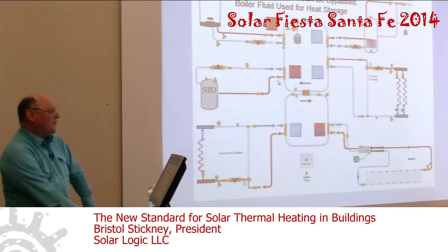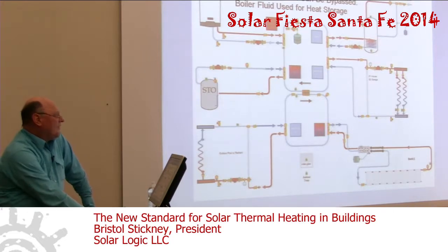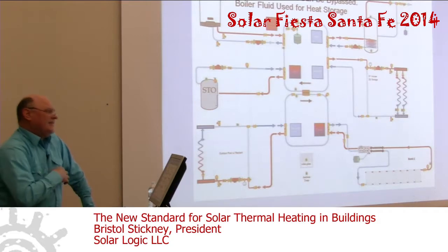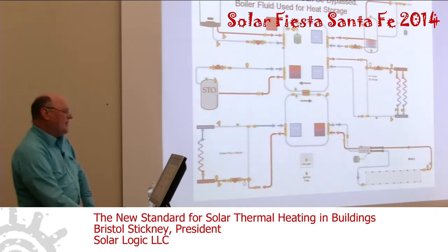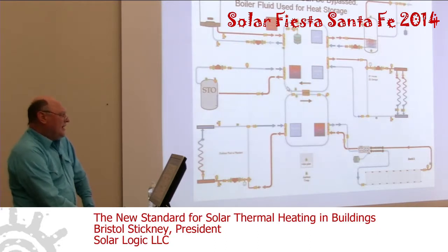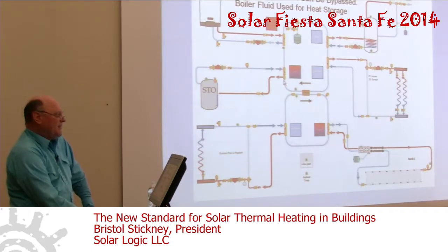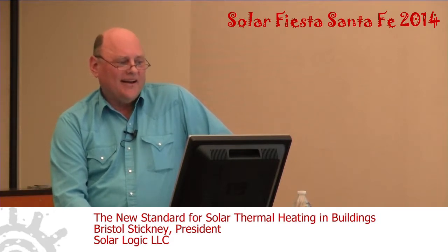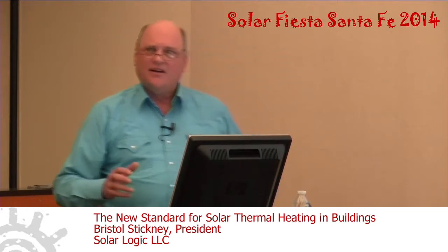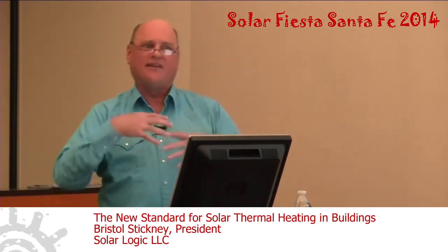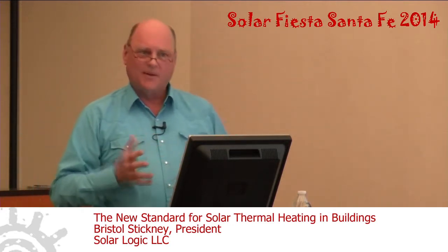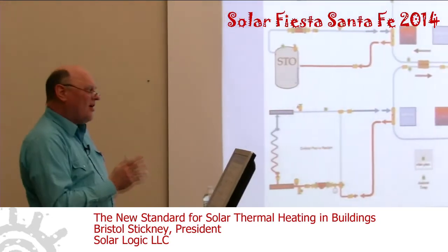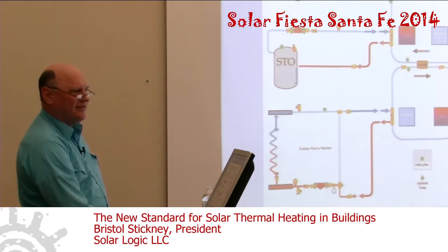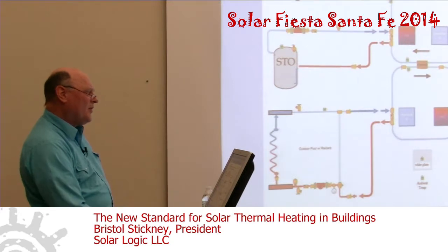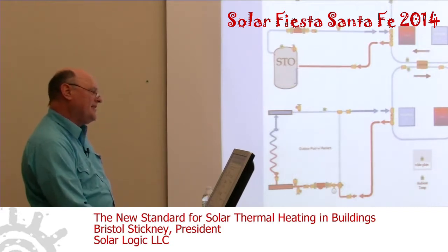One of the interesting things about the way we do this, and I refer to this as an innovation, is that if you follow this plan for your hot water plumbing system in your house, it gives you the advantage of either using or bypassing anything in the system simply by turning its pump on and off. So I know that in the past, solar heat system designers have racked their brains on how to connect things together and done some pretty inventive things, but they're very hard to control. If you do it this way, the control is simply, do you want to turn the pump on or off right now? And that's all there is to it. So if you want the boiler to turn on, you turn its pump on, and the boiler controls turn it on, and you deliver heat around the loop from the boiler simply by turning its pump on.